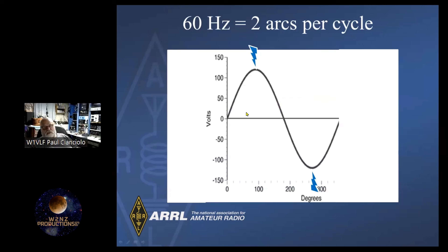So the end result is 120 hertz, 2 arcs per cycle. This is an important one, something anybody can do. You look at it and see this 120, 240, 360, 480, and you know it's power line noise related. At that point, there may be other things in there causing a problem, but this is a really solid indicator. Leave the problem to the power company - you can find out where it is, DF it. And don't bang on the poles again.